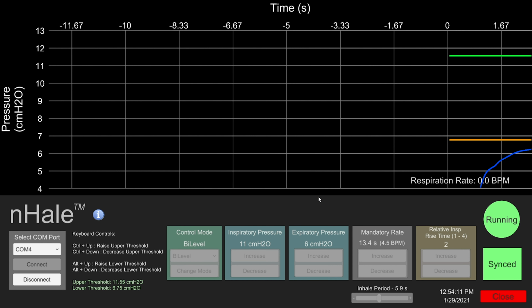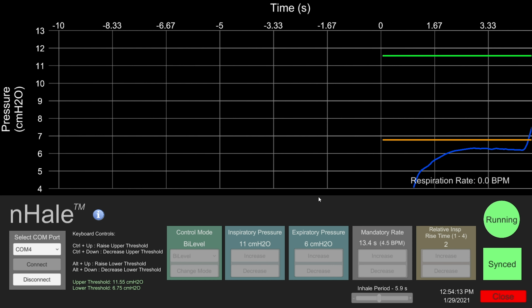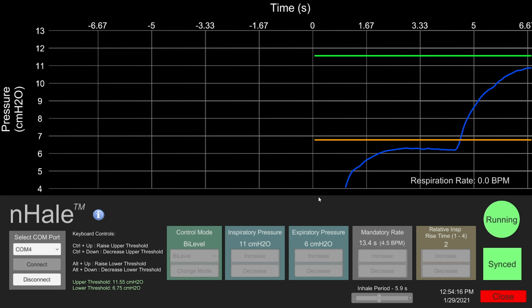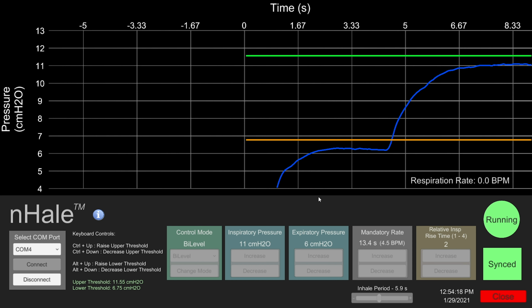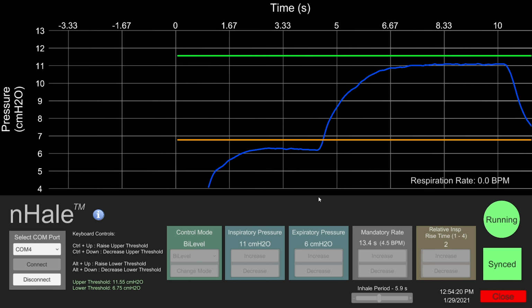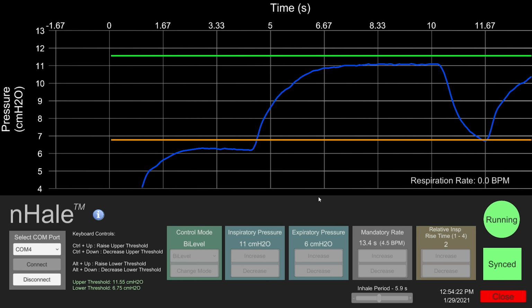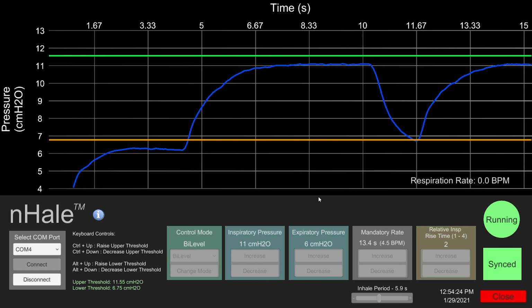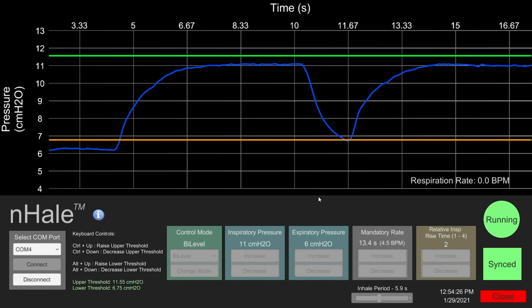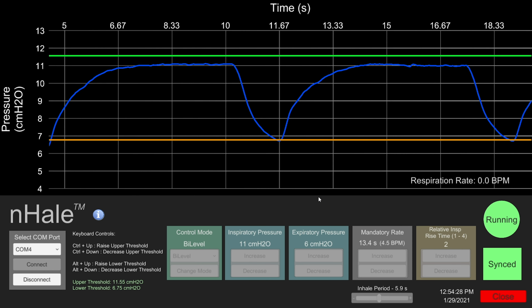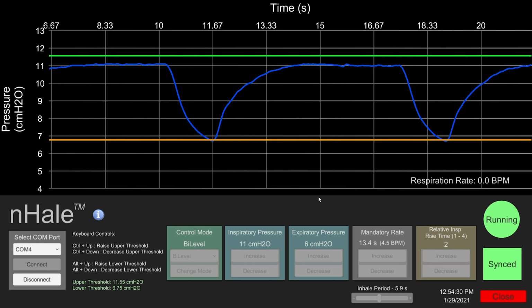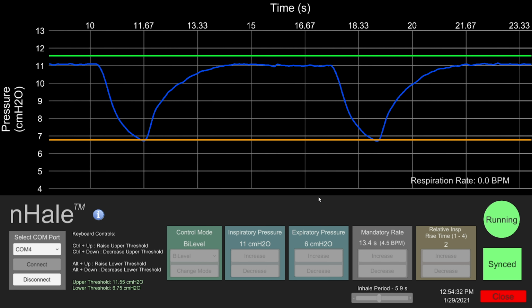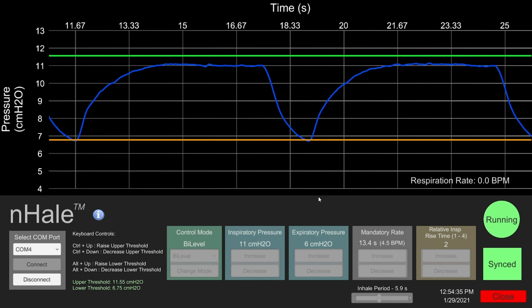As the device turns on, we begin to see pressure readings on our screen represented by a blue line. The green line represents the upper threshold and the orange line represents the lower threshold. The thresholds can be adjusted during therapy to help select the values that are most comfortable to the patient. Here, we increase the upper threshold and the line is updated on our screen immediately.